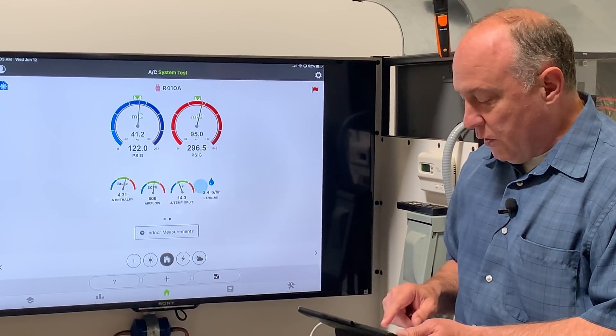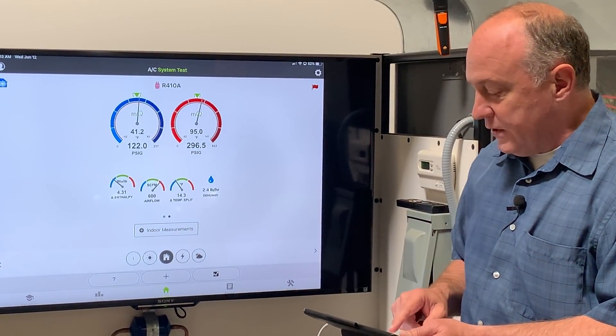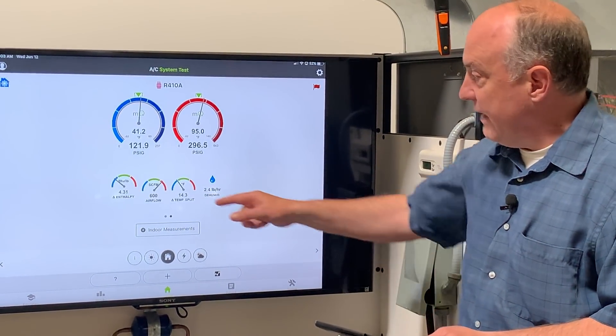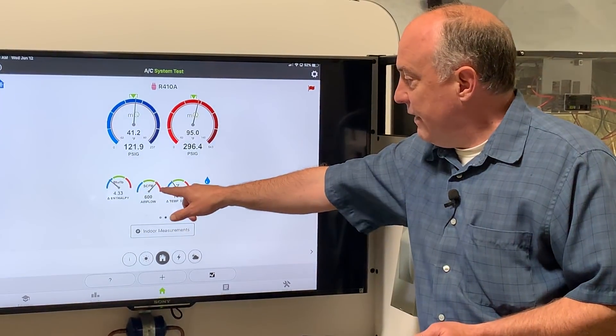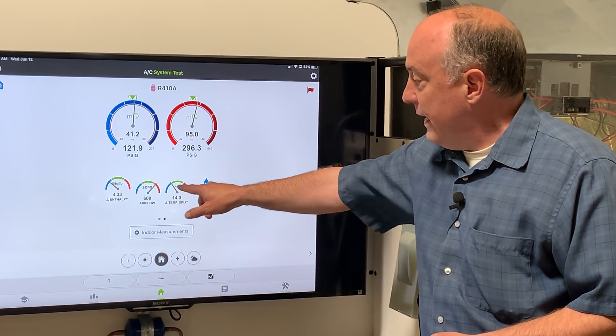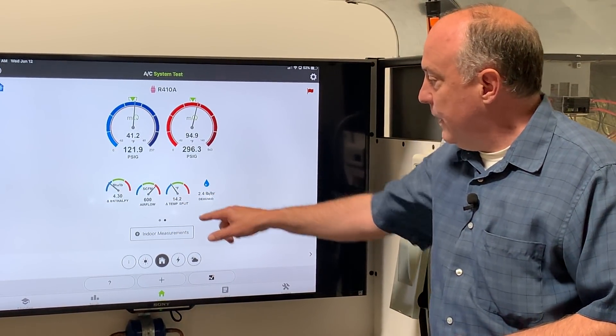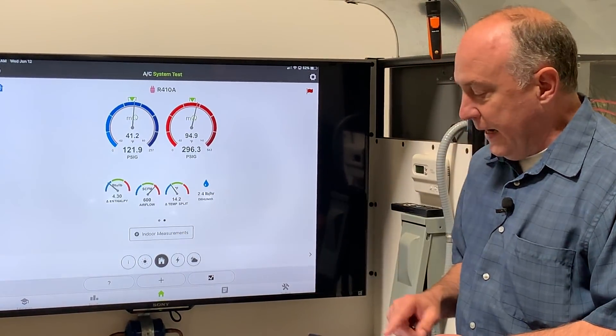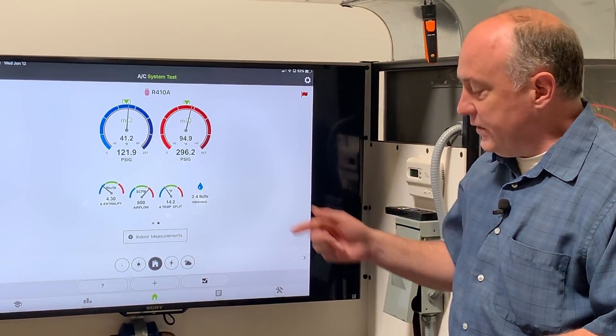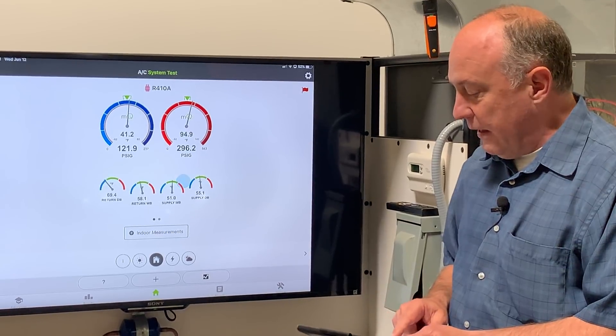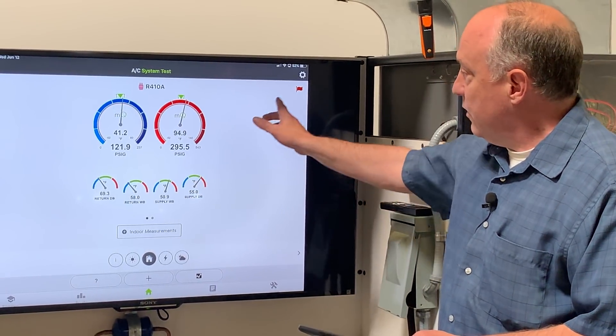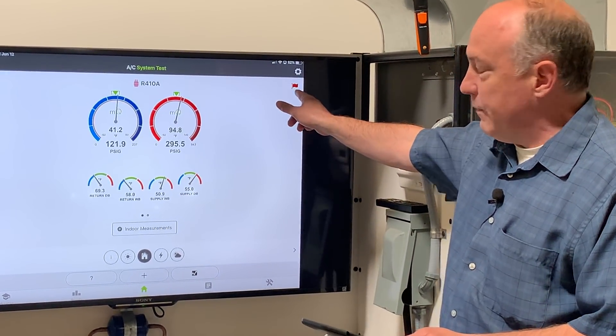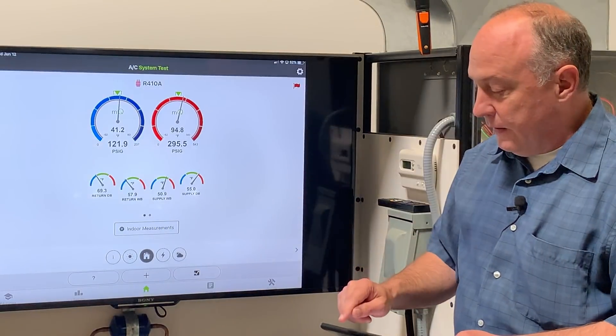I can scroll through and look at all my values here. I can see I have a low change in enthalpy, high airflow, and a low temperature split. All these different readings have a calculated target, so as we're looking here, it creates this flag.